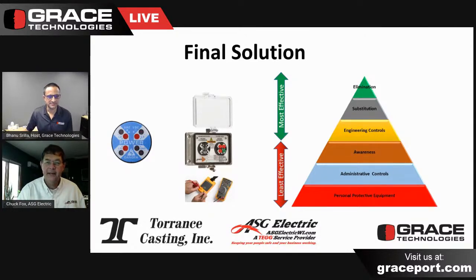One of the other interesting parts of landing these various terminations was whether the size of the lug would reduce the gapping distance between the different levels of busing, making it easier to trigger an arc flash event by closing the gap in the original engineering busing. When you look at the distances of those bus plates, you wouldn't want to put two lug assemblies back to back and close that gap by taking a third of that distance away.